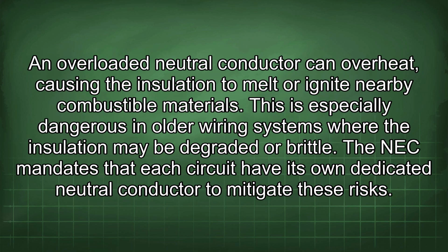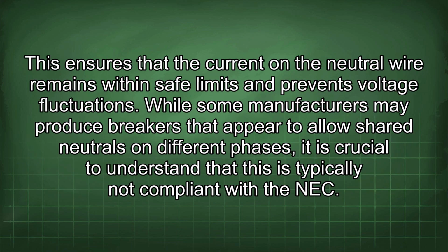An overloaded neutral conductor can overheat, causing the insulation to melt or ignite nearby combustible materials. This is especially dangerous in older wiring systems where the insulation may be degraded or brittle. The NEC mandates that each circuit have its own dedicated neutral conductor to mitigate these risks. This ensures that the current on the neutral wire remains within safe limits and prevents voltage fluctuations.